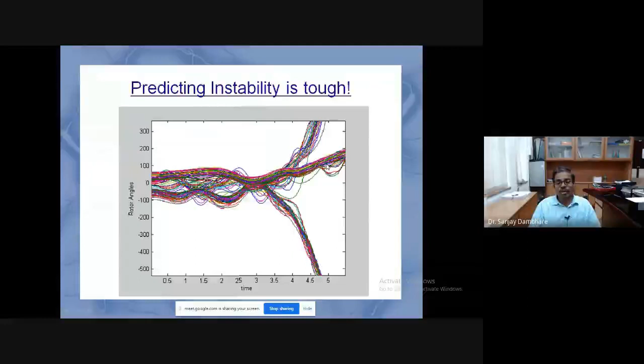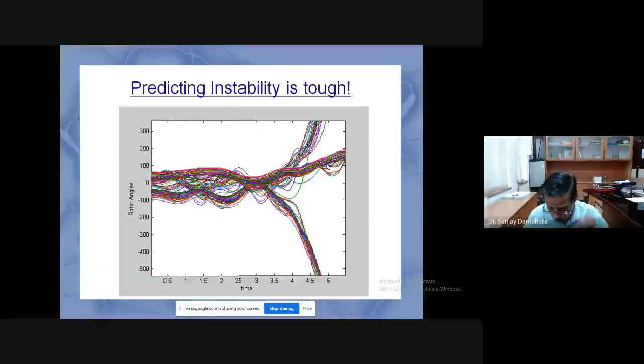You can get the wide area measurements, you can get the system data, and based on that you can run some analytics to decide where the system is to be separated. If the load and generation are not balanced, right, then the island will not survive. The island will again go into tripping.